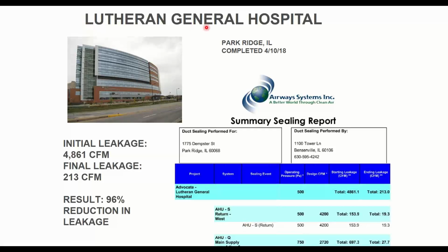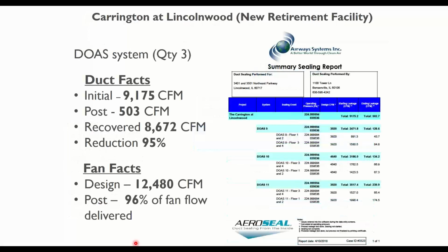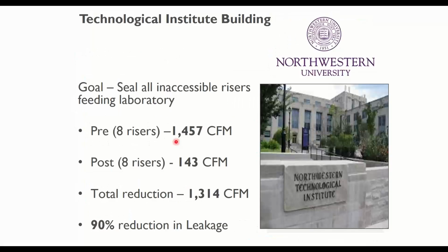This hospital was okay with their name being out there because it was a newer duct system. So initial leakage went from 4,800 down to 200. Here's another one. This was seven separate air handlers that added up to 21,000 CFM of leakage, got it down to under 900 for those seven systems combined, 96% reduction, right? And there's just tons of examples like this. This one is not a hospital, but it's a retirement facility, 95% reduction, 9,000 down to 500 CFM. You're saving 8,672 CFM of leaking air. And there's just example after example after example. There's no shortage of cases.